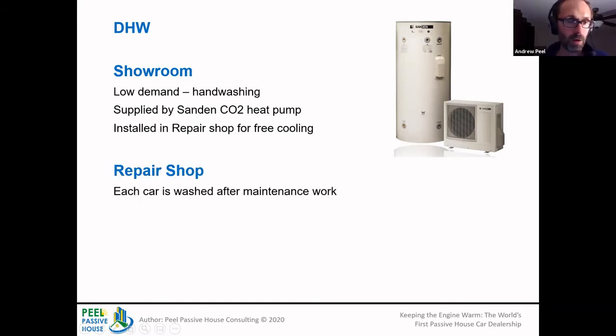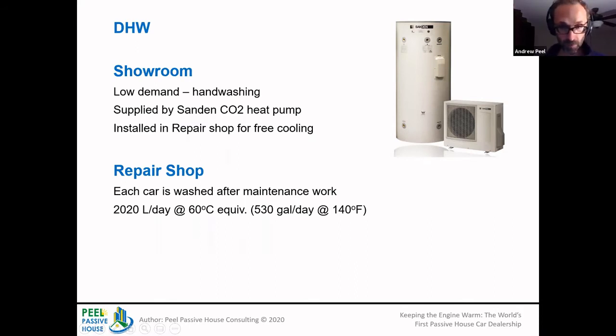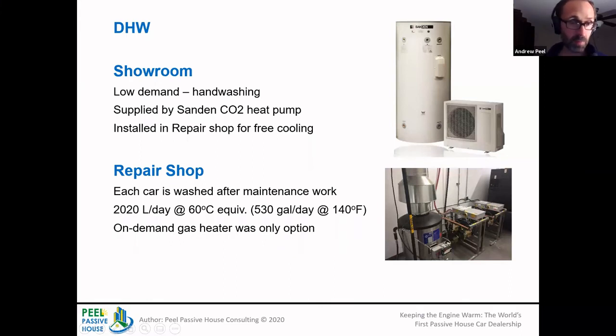And then in the repair shop, they actually mentioned a car wash. They use hot water. It's not necessarily common for all cars, but as part of their standard service, they use hot water to wash the cars, and every car that's serviced gets a car wash. And it's quite a bit of water: 530 gallons per day, as you can see, at 140 Fahrenheit. And the only option to keep up with this demand is an on-demand gas heater. Any regular heat pump system, like these CO2-based systems, can't produce enough hot water fast enough to keep up with that demand.